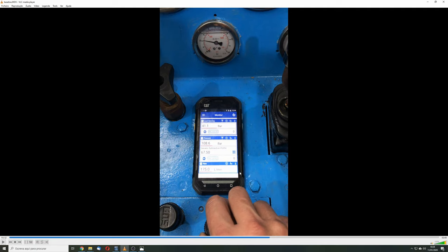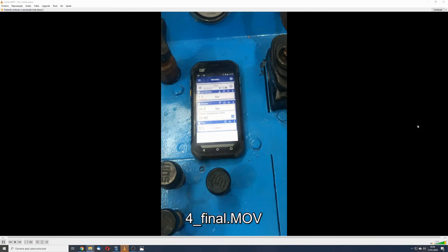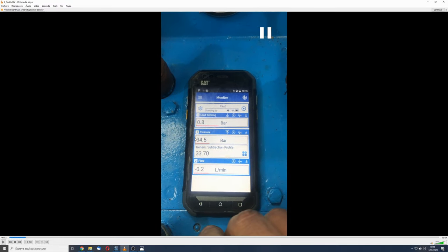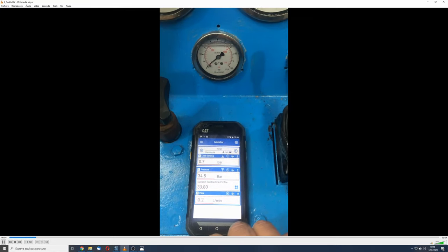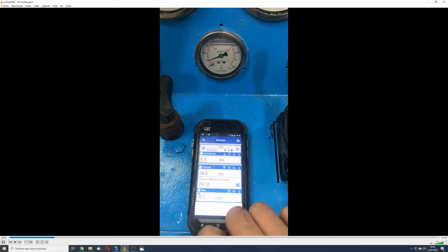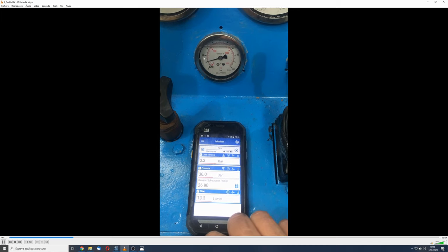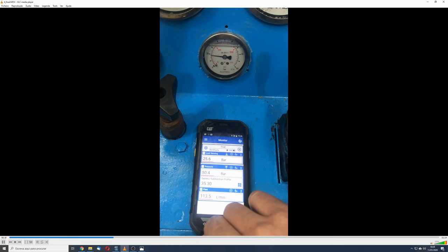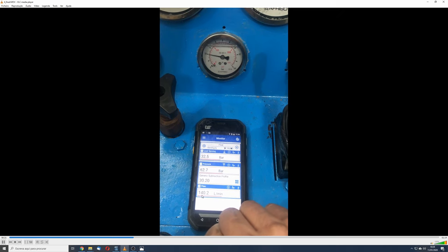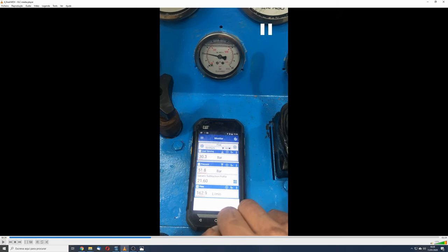And now have a look at this very same system after we've lowered the delta P. So we right now are facing the standby of 34 bar. I'm doing basically the same thing, increasing the pilot pressure, the flow goes up. And wait for it. Do you see the difference? Right now our instability is far less aggressive, and actually above 160 liters the self-oscillations disappear altogether. So this means that our lower setting improved that as well. Pretty cool.